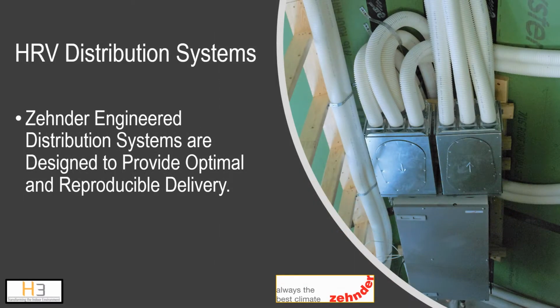The most effective way to deliver low volume, low velocity ventilation is via a distribution system matched to the requirements of low flow, low volume. It can also include sound attenuators, manifolds, registers, dampers, and trim components. These types of systems are proven to deliver predictable and reproducible results. Optimizing, regulating, and balancing flows of both supply and exhaust results in getting the most out of these HRV systems.